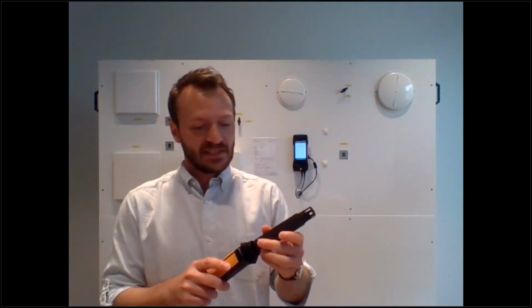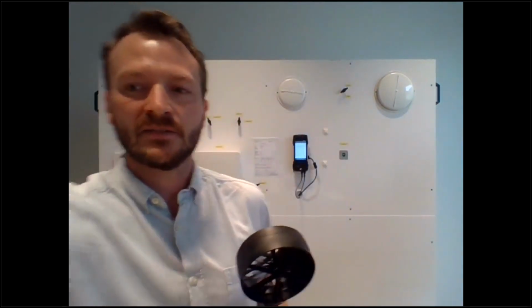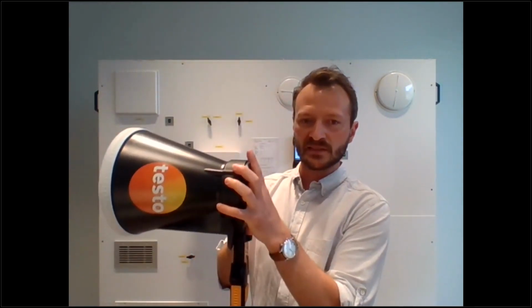If you're interested in air velocity, commissioning, and adjusting, you can also use other probes like CO2 and measure other parameters with the same instrument, just what you need and want to measure. I can also show you that the flexible Bluetooth handles can be connected here to the funnels without any problem. It fits as well, and you can start and stop the measurement just with a click on this button, so you don't need two hands. You can put it up on the ceiling and click the button to measure the volume flow.